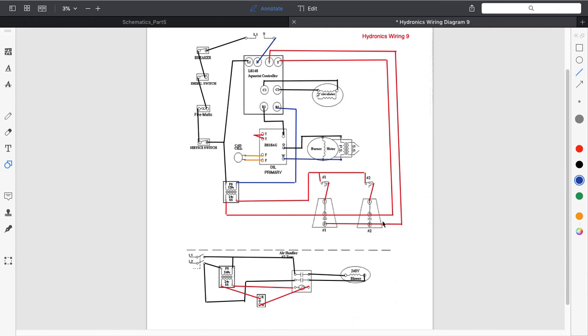When you're in the field, always double check this wiring because it's very easy to mess up where you've put the T and the T. Remember, the aquastat also has a transformer. So you don't want to put 24 volts or 48 volts accidentally across one of these zone valves or through a thermostat.